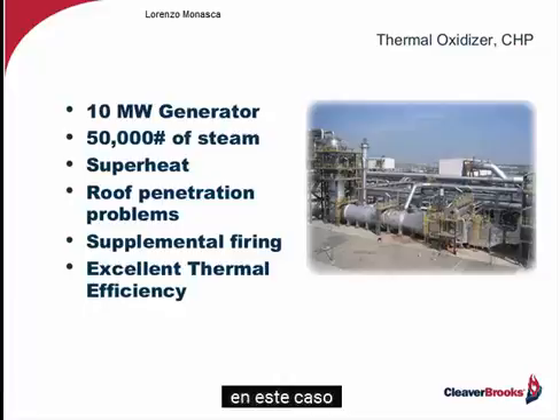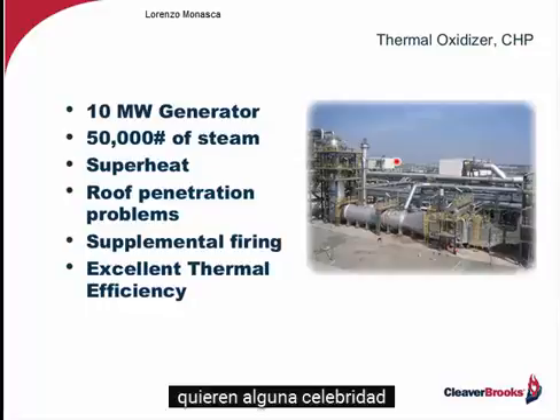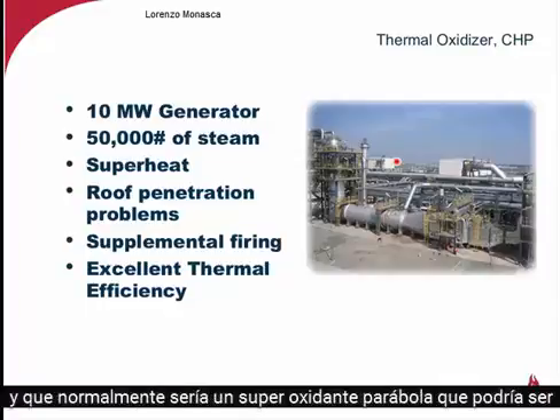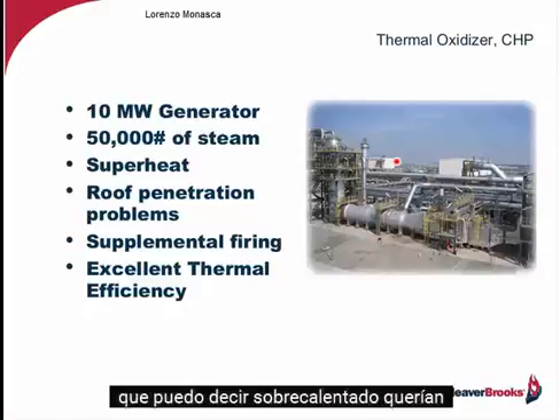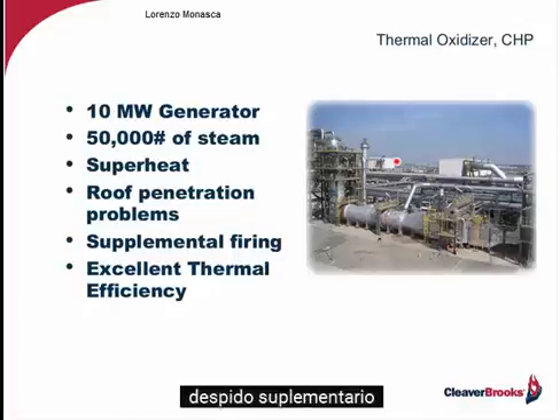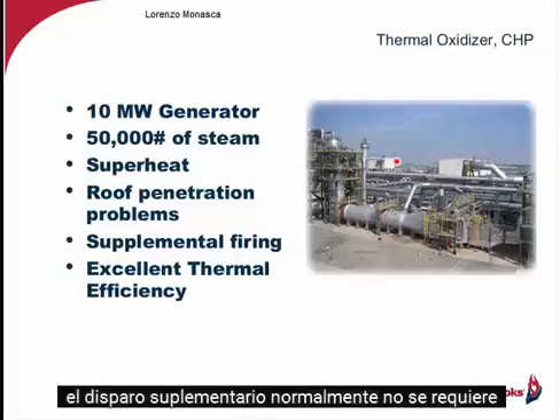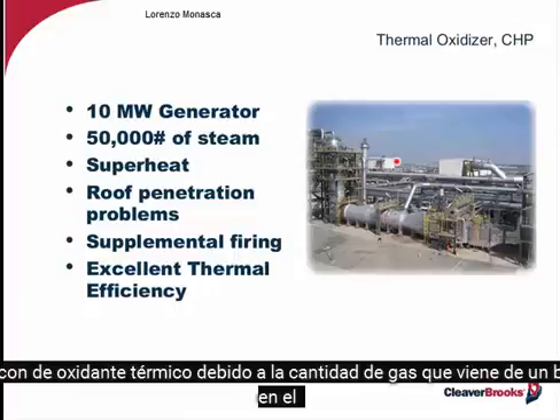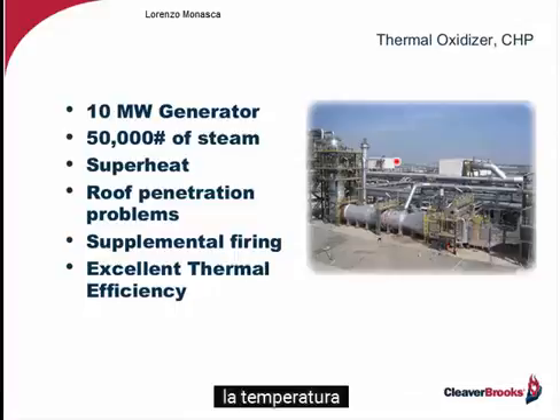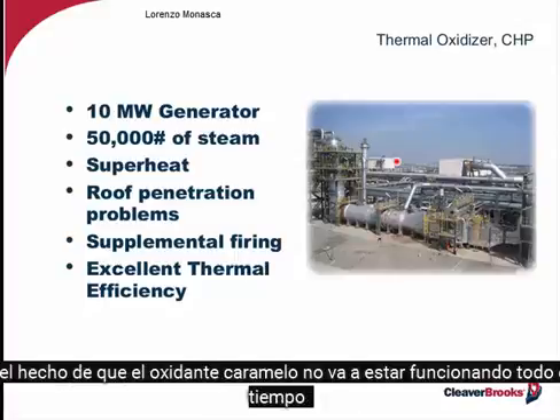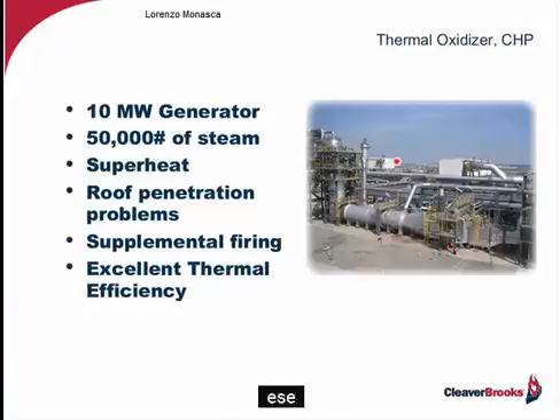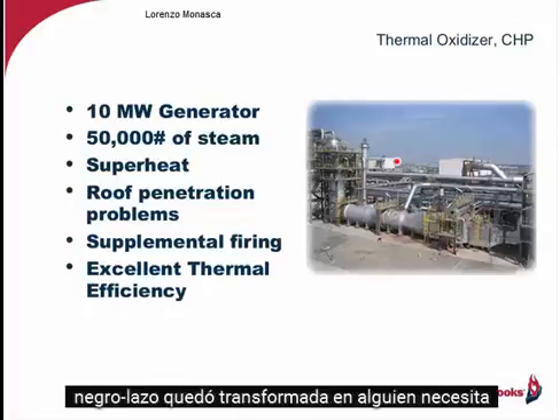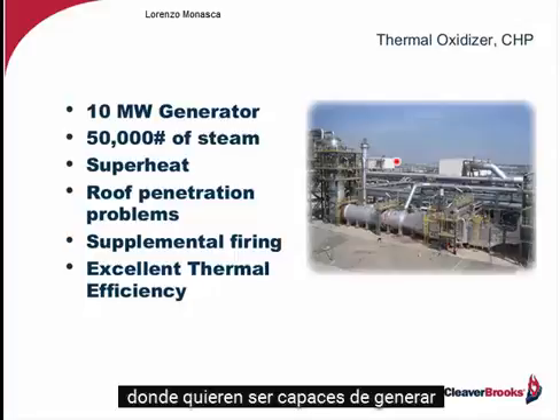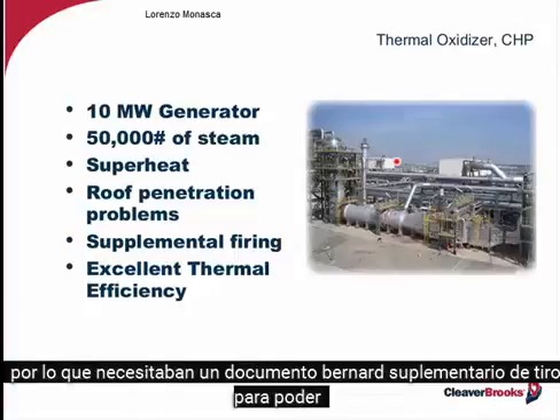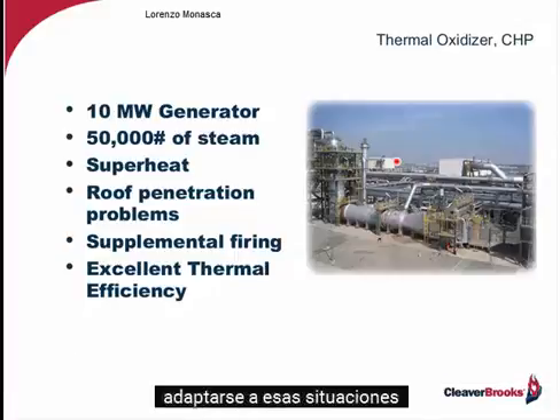Now, in this case, they want some superheat. And normally with a thermal oxidizer, superheat could be a problem, okay? I shouldn't say superheat. They wanted supplemental firing, okay? And the supplemental firing normally is not required with a thermal oxidizer because of the amount of gas coming off of it and the temperature. But in this particular case, they were concerned about the fact that the thermal oxidizer is not going to be operating all the time. They've got certain processes that are not operating all the time, so they don't have to incinerate those fumes. But they've got process and facility needs where they want to be able to generate the steam to satisfy those needs. So they needed a duct burner then, supplemental firing, to be able to accommodate those situations.